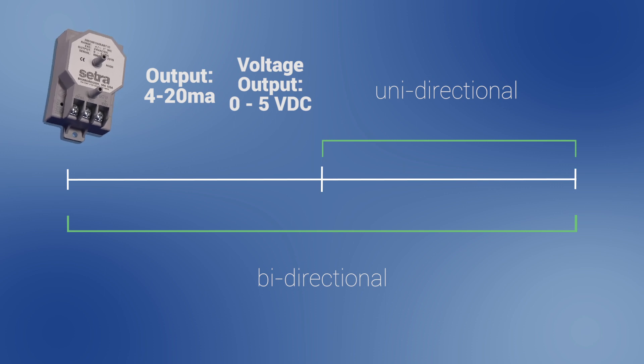The pressure transducer gives a linear and proportional output as pressure is applied. For example, a unidirectional pressure range of 0 to 10 inches of water column with a 4 to 20 milliamp output would output 4 milliamps at 0 pressure, 12 milliamps at 5 inches of water column, and 20 milliamps at 10 inches of water column.